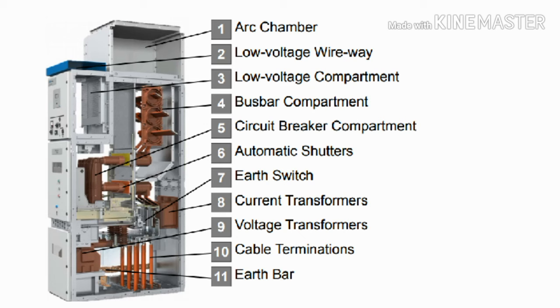Eighth is the current transformer. The current transformer helps to measure the current flow from the downstream and displays it in the low voltage compartment section on the ammeter. Ninth is the voltage transformer, which is placed on the downside of the circuit breaker — the bottom part of the switchgear panel.